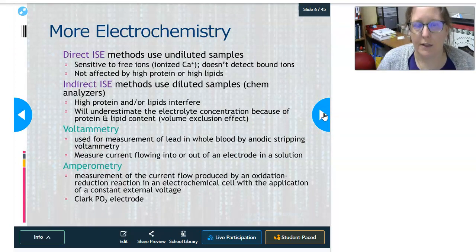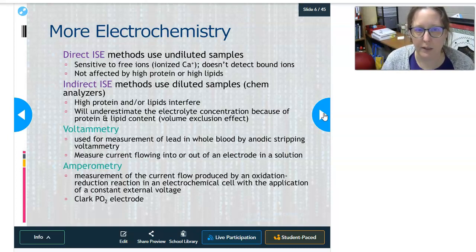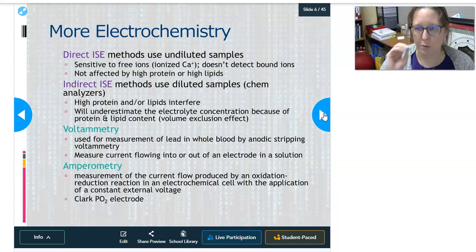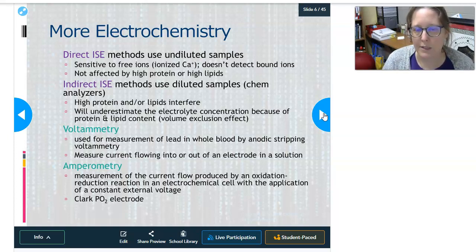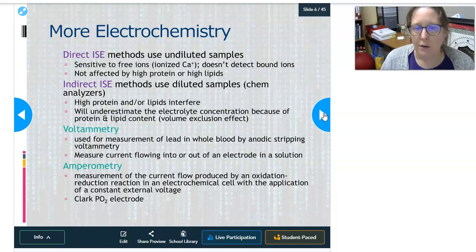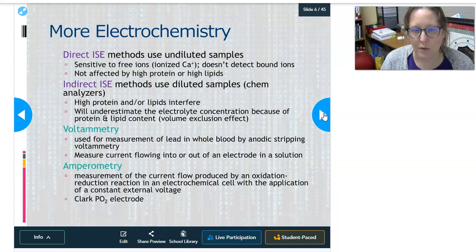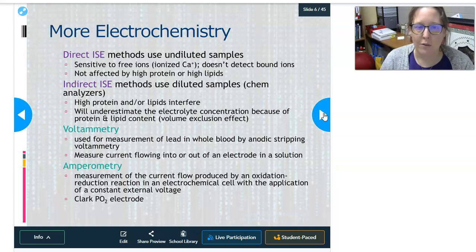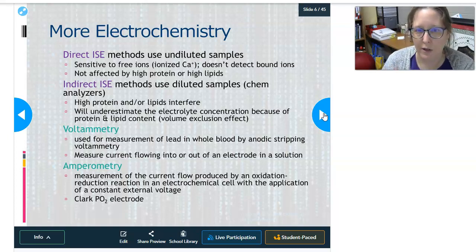There are two ways to measure with ion-selective electrodes: direct and indirect. Direct ISEs use undiluted samples — pure serum or plasma — and are sensitive only to free ions. For example, they can measure ionized calcium but don't detect protein-bound calcium. About half of calcium is ionized and half is bound to protein; the ionized portion has the physiological effect. Direct ISEs are also not affected by high protein or high lipid levels. Indirect ISEs use a diluted sample and are found in large chemistry analyzers, where high protein or lipid levels can interfere with electrolyte measurement.